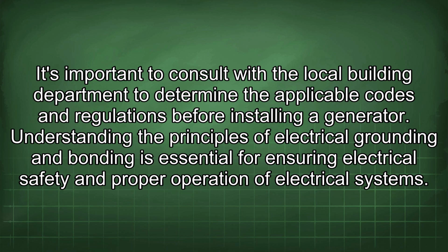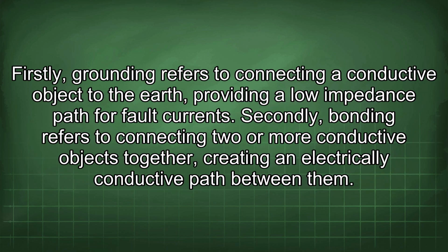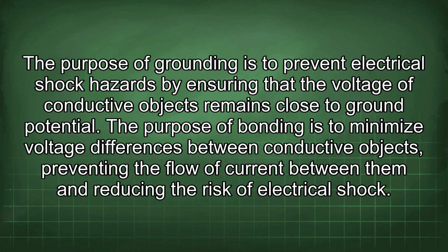Understanding the principles of electrical grounding and bonding is essential for ensuring electrical safety and proper operation of electrical systems. Firstly, grounding refers to connecting a conductive object to the earth, providing a low impedance path for fault currents. Secondly, bonding refers to connecting two or more conductive objects together, creating an electrically conductive path between them. The purpose of grounding is to prevent electrical shock hazards by ensuring that the voltage of conductive objects remains close to ground potential. The purpose of bonding is to minimize voltage differences between conductive objects, preventing the flow of current between them and reducing the risk of electrical shock.